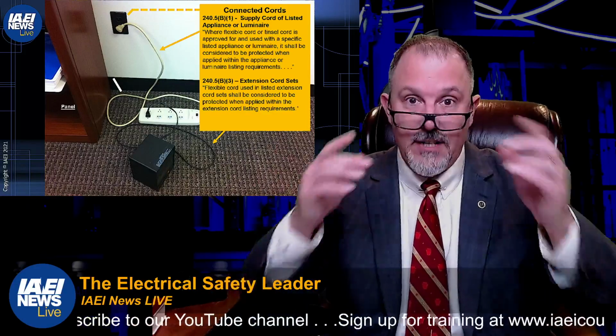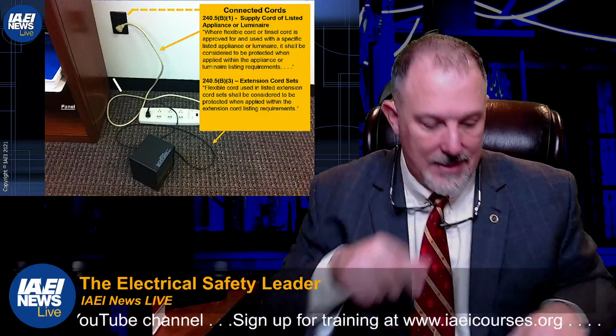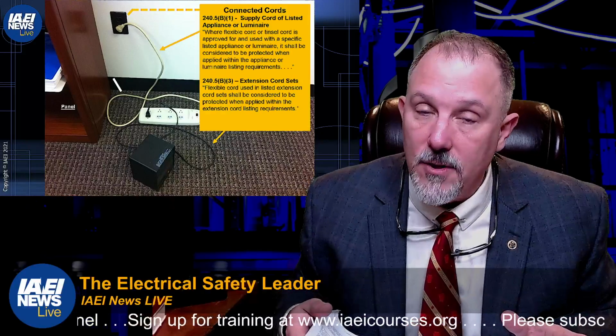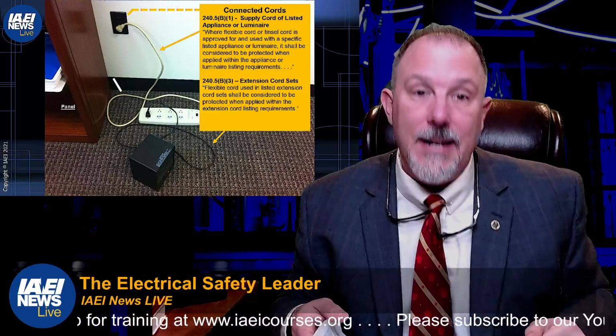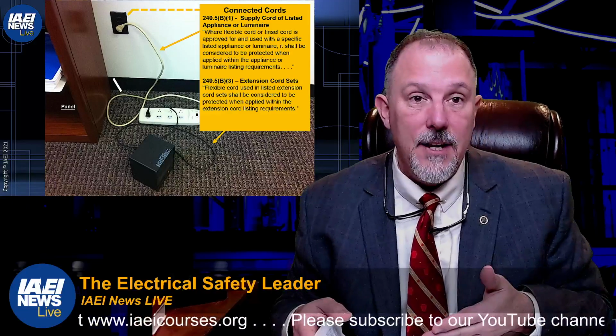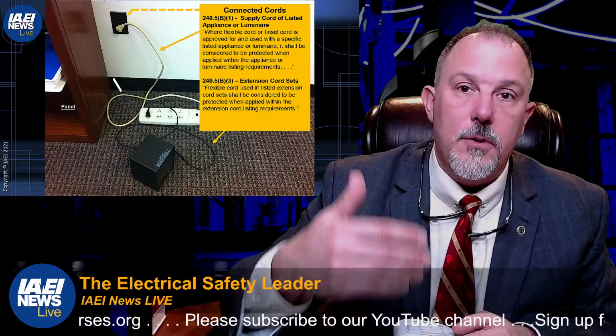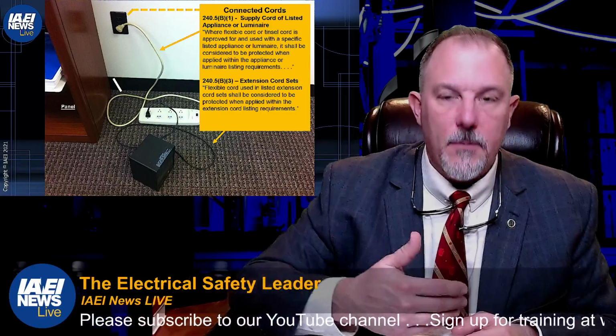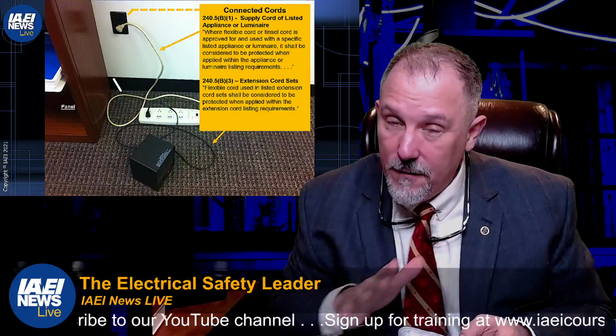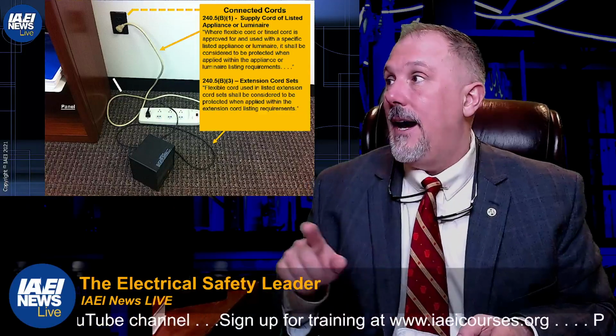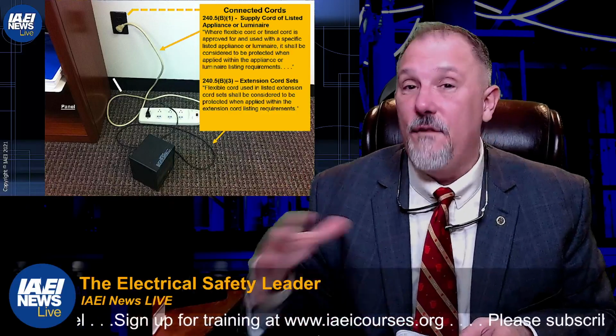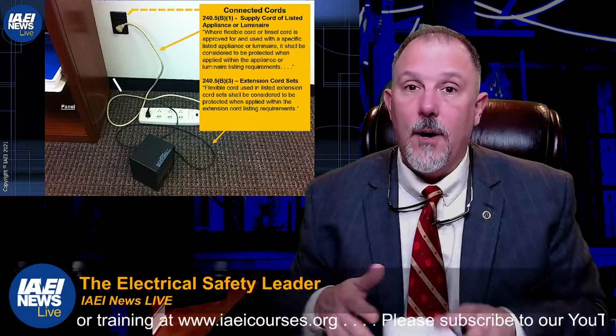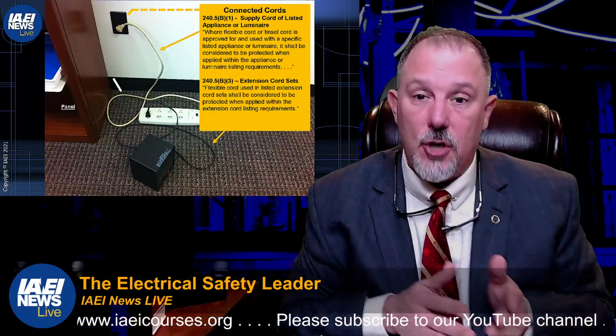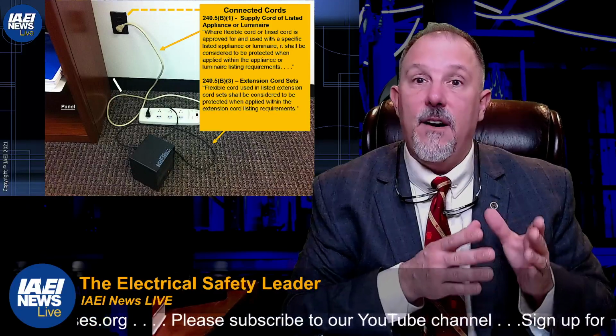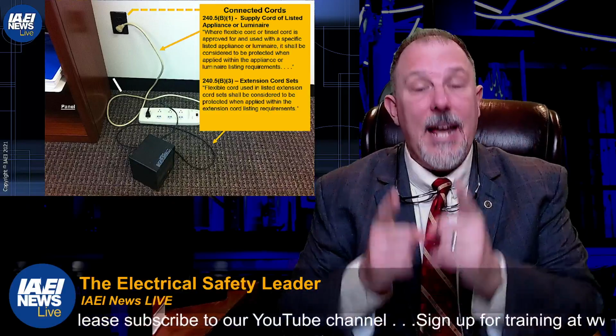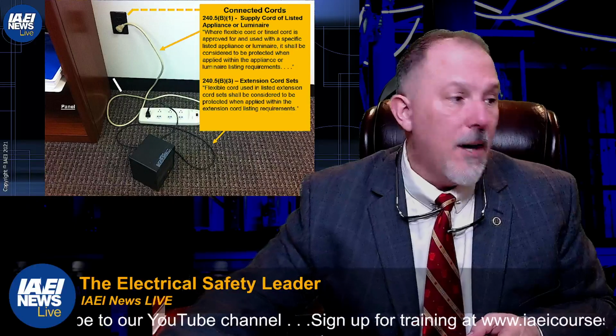Now, there have been cases where, for example, a luminaire was installed in a crawl space and someone died. Boom, 210.8 requirement. We get the justification to provide the additional protection based upon statistics. With 210.12, you may say, I've had lighting luminaires that have caused electrical fires, and you ask, where are the statistics? You look at the CPSC data, which shows the statistics of electrical fires that have occurred.